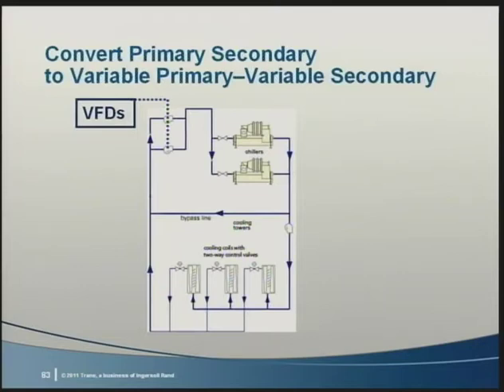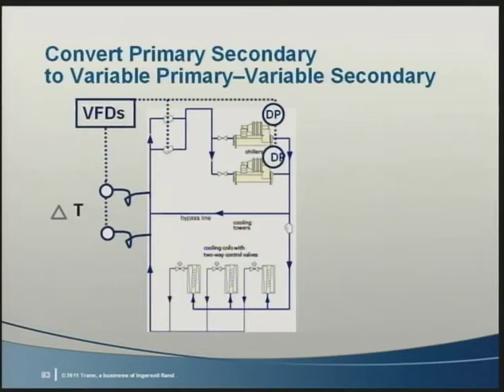Next, if they aren't there already, install temperature sensors in the return line from the system and to the chiller. Control the pump VSDs so that the return temperature to the chillers is a degree or two lower than from the system. This ensures a little excess flow in the bypass line all the time, but more importantly, that the system chilled water set point is always maintained. Finally, install flow sensing devices such as DP sensors at each chiller to ensure minimum flow rate. If the temperature control of the pump VSD results in flow approaching the chiller's minimum, this sensor will speed up the drives on the pumps. So, there are a number of options to convert to VPF.